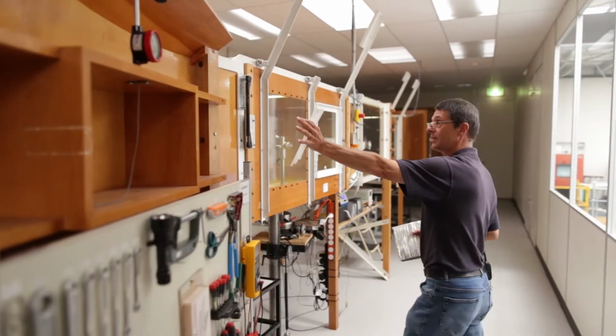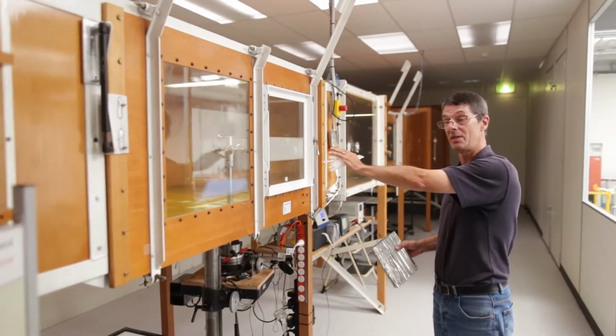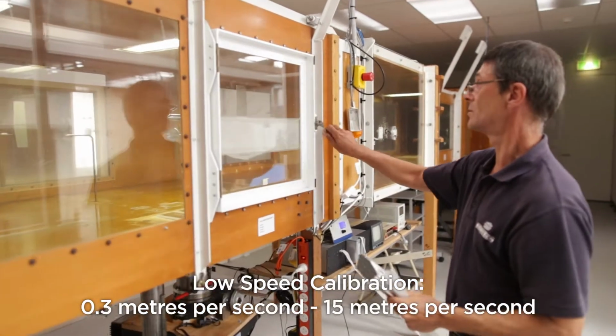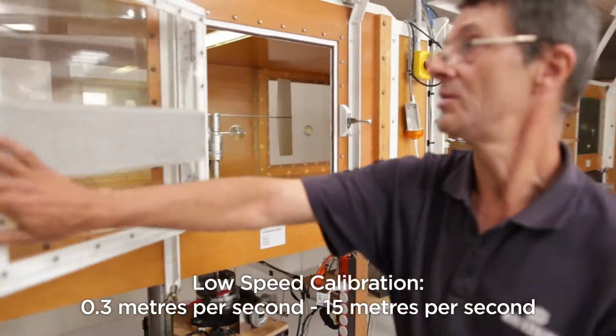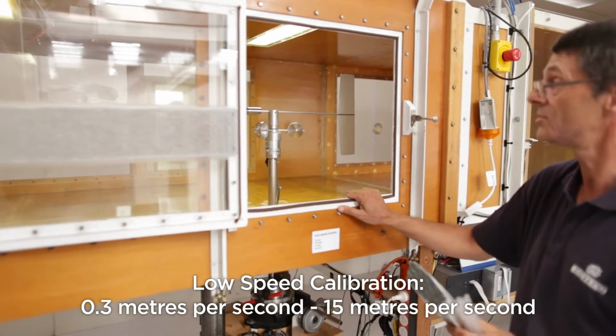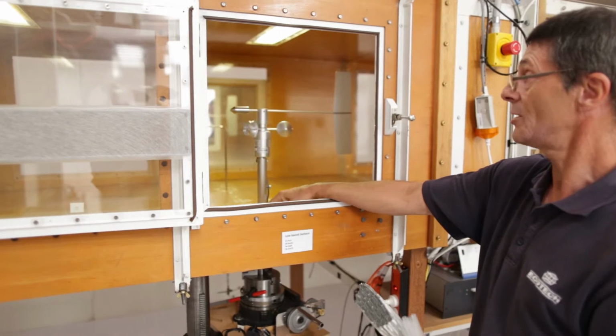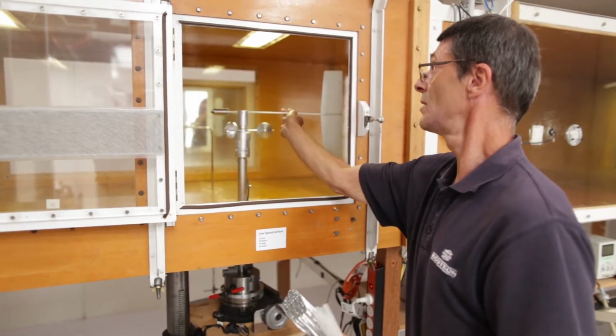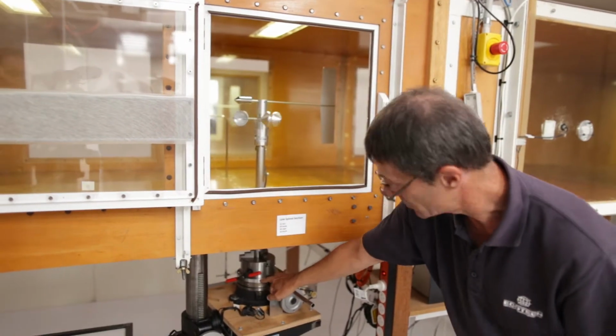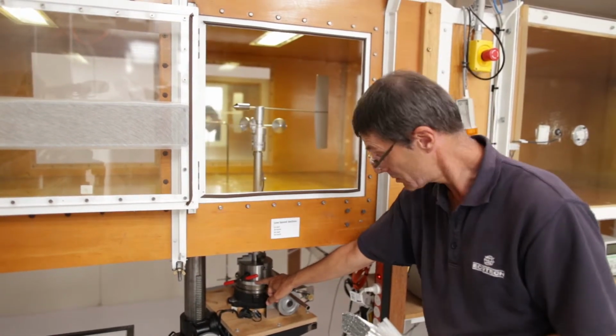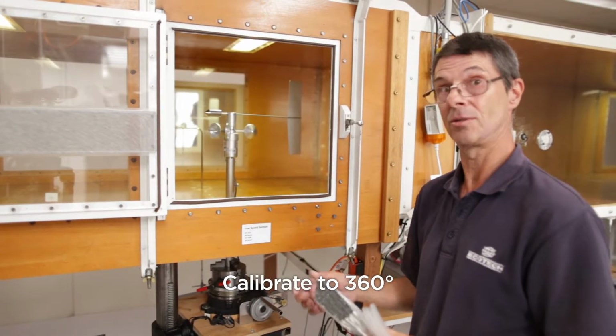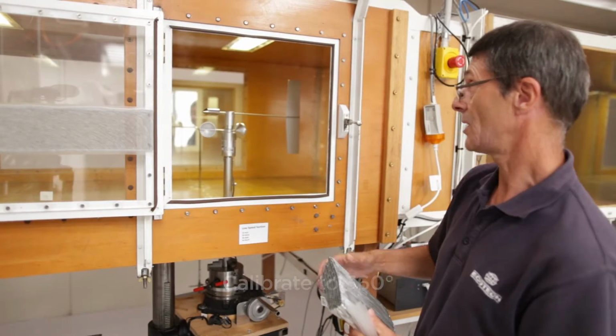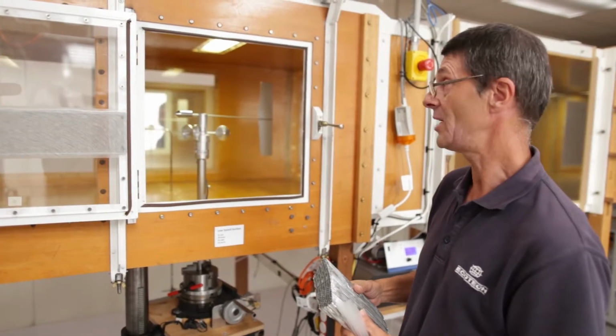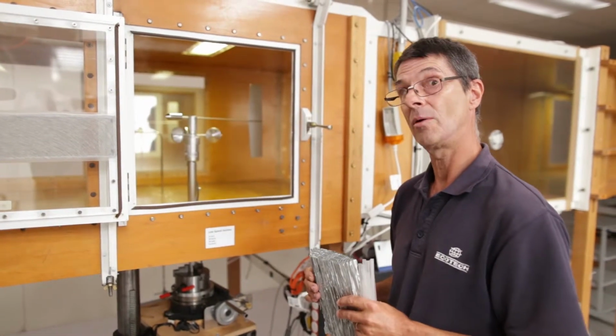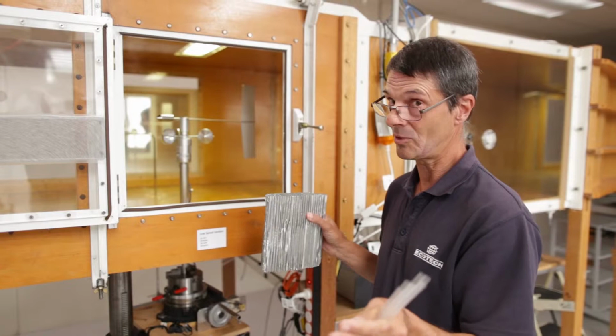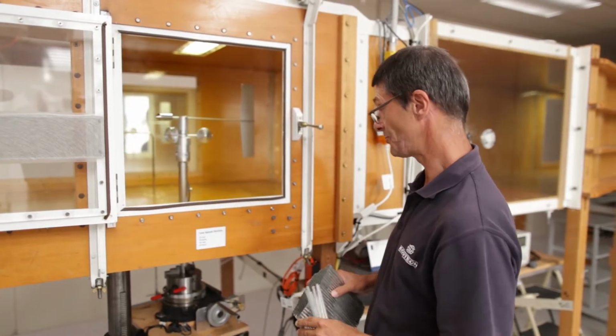There's some compression of the air here, which leads into our low-speed test area where we can do calibrations from 0.3 metres per second up to 15 metres per second. I have an anemometer set up in the tunnel at the moment with a wind vane. That's all mounted on a post which is connected to a rotary dividing head, or mechanical dividing head, which allows us to calibrate wind direction through 360 degrees. I can make the speed in the tunnel faster or slower depending on the specific requirements of the customer. So we can calibrate anywhere between 0.3 and 15 metres per second in this area.